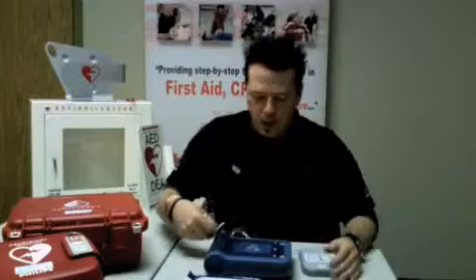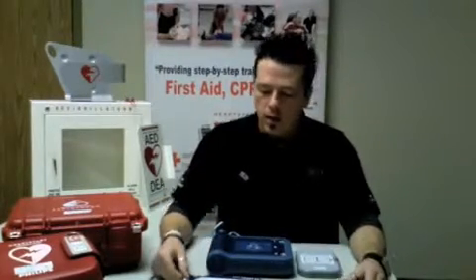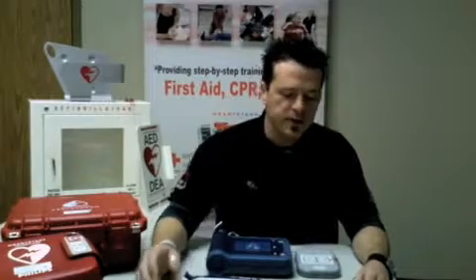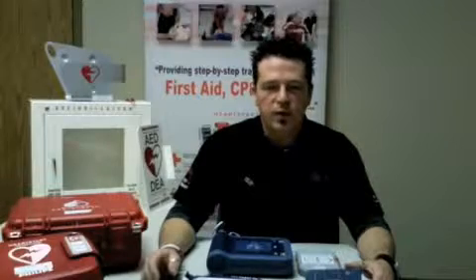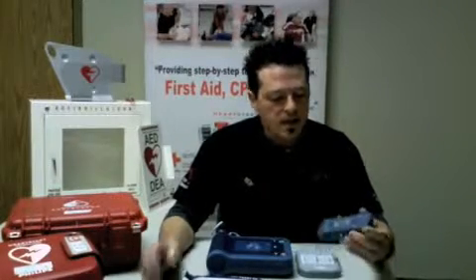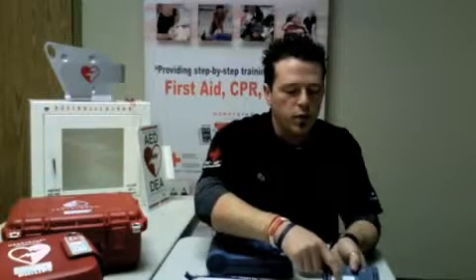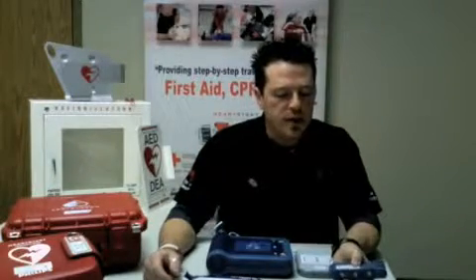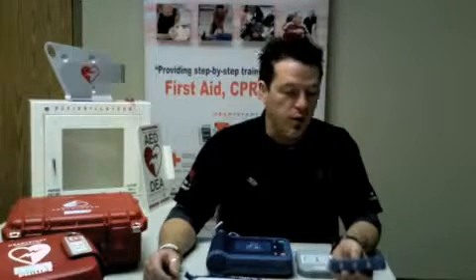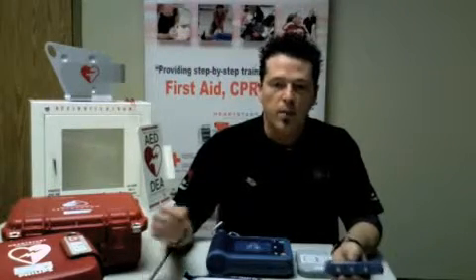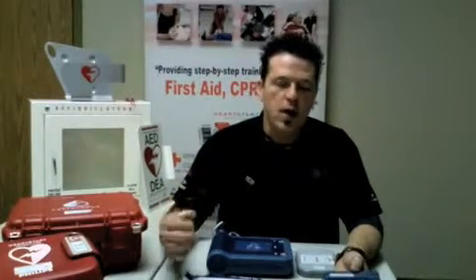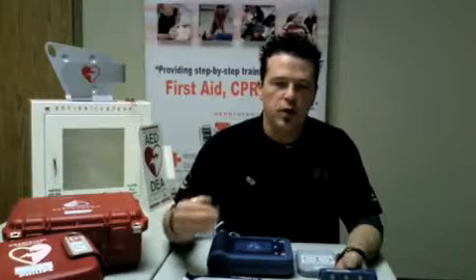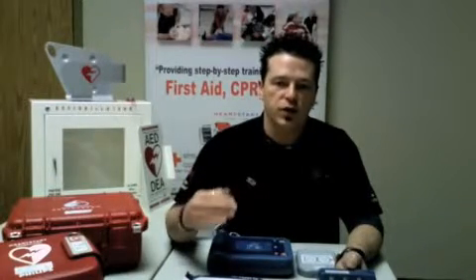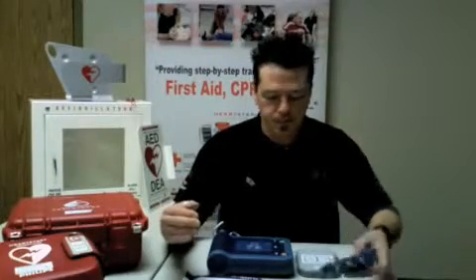Now there are two things before I actually get into the servicing that are important to know. The first is to understand that the battery itself, which is basically a big 9-volt battery, has a 5-year shelf life. In this case, the shelf life says here 01/2011, which means that if I install this battery in January 2011 or before, from that point on, the battery should be good for 4 years. So as long as the battery is installed before the install-before date, from that point on, the battery is good for 4 years in the defibrillator.